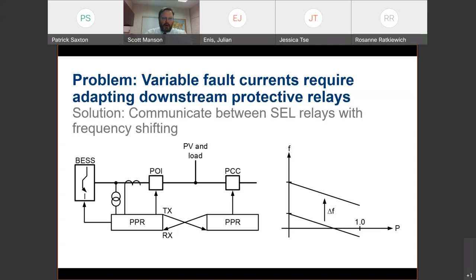Here's an example. You put a PPR, programmable protective relay, at the inverter, and when the utility goes away, you tell the inverter, shift my frequency. And instantaneously, these very fast inverters will shift the power system frequency, and all the downstream relays will see, oh, we're now an island. I will change my protection coordination curves, and within 16 milliseconds, you are back on deck, you never had an outage, and your customers are protected again. This is a very simple answer that protective relays offer you for solving a huge problem. And the relays are already out there.